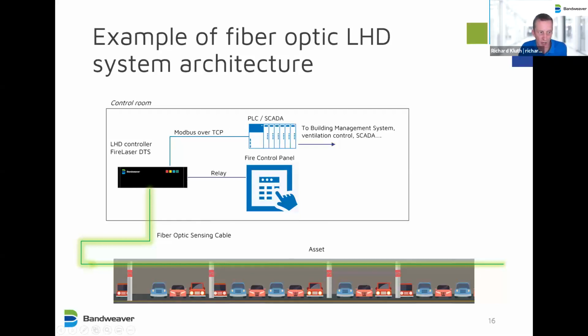This is typically to the SCADA or building management system, and Modbus contains more detailed information, including the precise temperature and the location. So in addition to basic triggering of fire alarms, other systems can be activated accordingly.